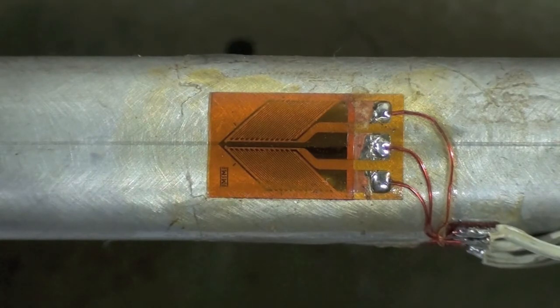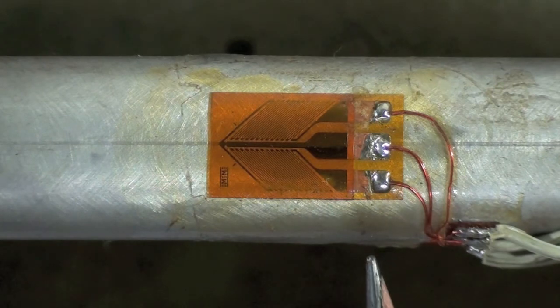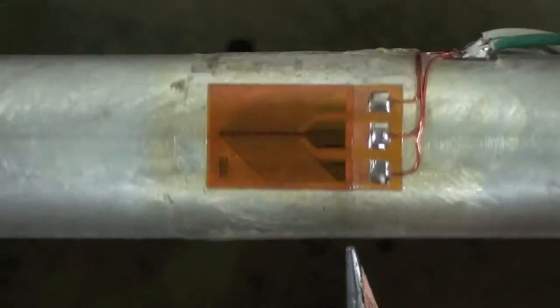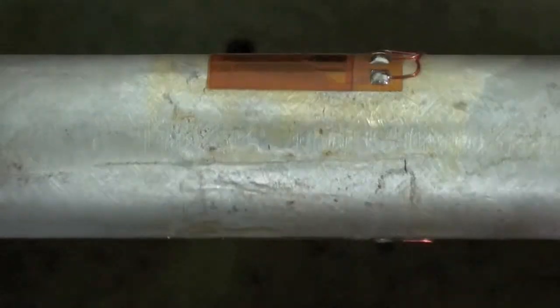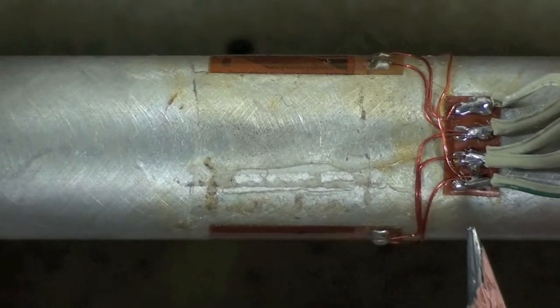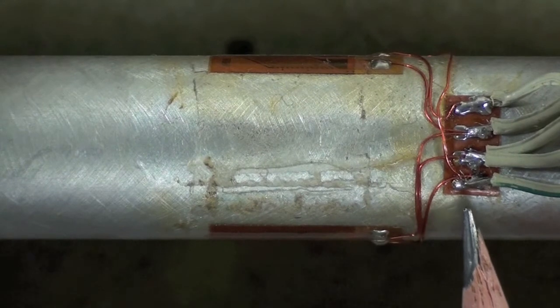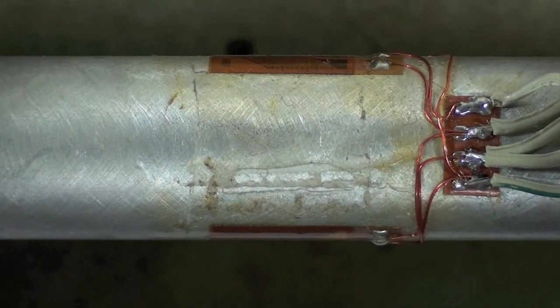As a practical example, two micromeasurement gauges of the type 187 UV are bonded on diametrically opposite points on a round bar. The gauges are interconnected at this point to form a full Wheatstone bridge, and from here lead wires can be connected to an instrument for measuring torque.